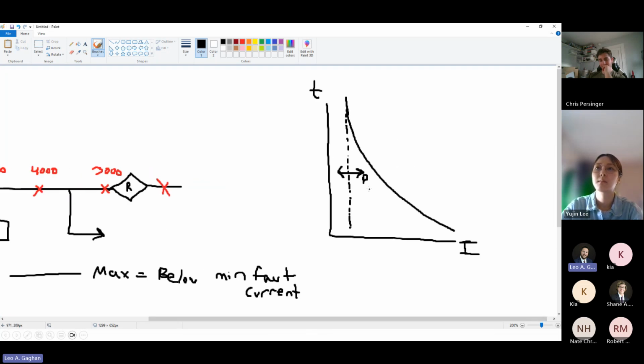So with that, let's say you had a downstream recloser. Okay, I'll make that guy green. You've got that downstream recloser that you want to be faster than your relay. You need to set your settings so that you're slower than them, they're faster than you, right? You've got your fault current for this fault here. All right, you can see recloser is faster on that time scale, relay is slower. That's your goal.